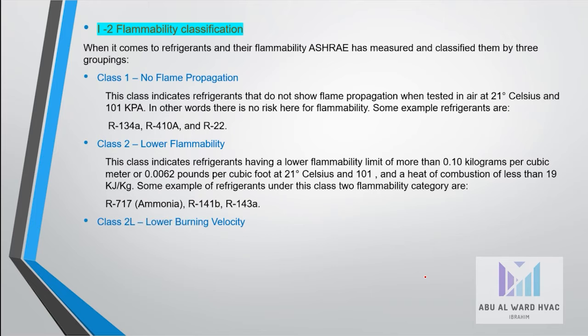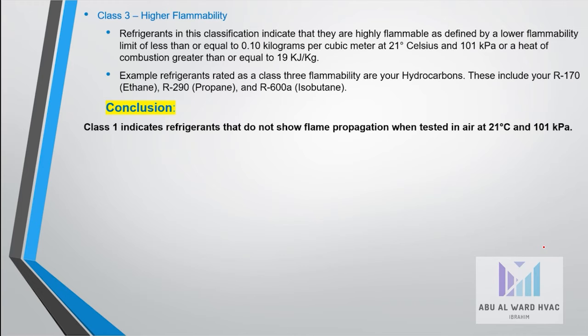Class 2L indicates lower burning velocity, where the burning velocity is less than or equal to 10 cm/s, such as HFO-1234yf, which is used as an automotive refrigerant. Class 3 is higher flammability: refrigerants in this classification are highly flammable, as defined by a lower flammability limit less than or equal to 0.1 kg/m³ at 21°C and 101 kPa.